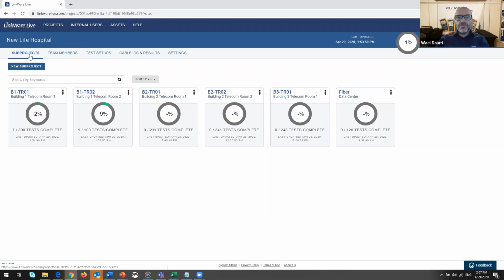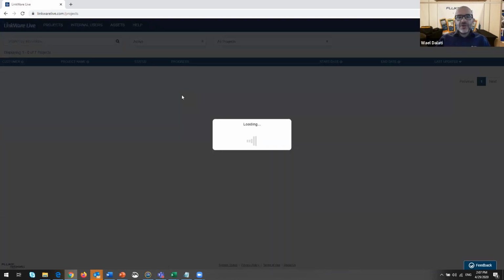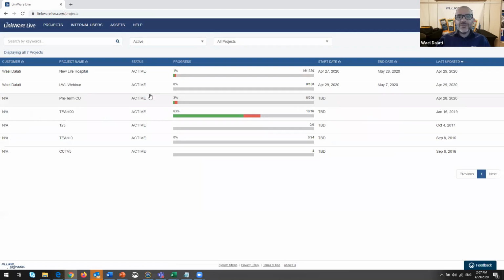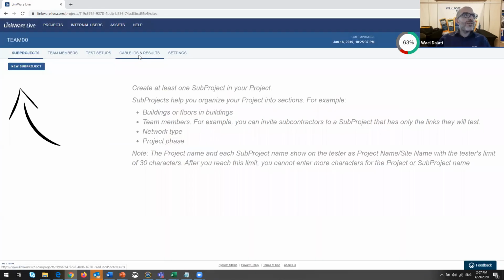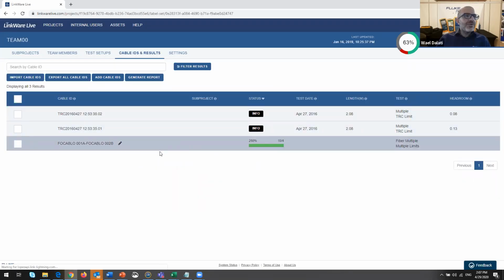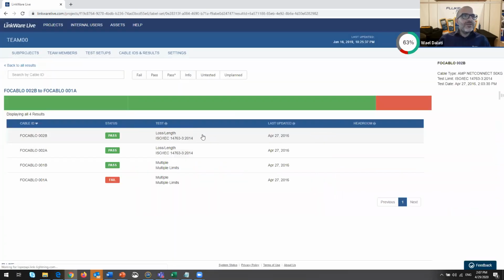But for calibration, if the unit is out of calibration, you will be able to see what I'm seeing here, and I will share with you a project where we did a test without calibration. It is done with our demo units, since we own demo units that are not allowed to be calibrated. So we can immediately spot that. And I can show you a test result that we have here.